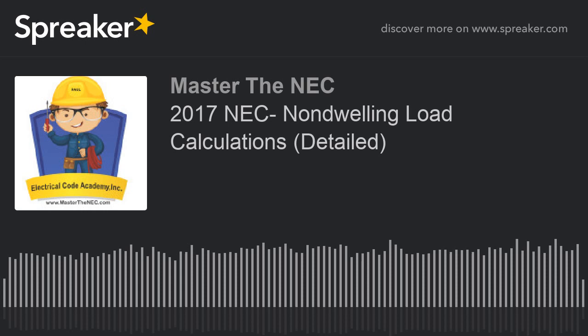Now, that's our calculated amps. We know it now. So now we have to size the service. Okay, now we know that we got to have a conductor that's going to at least handle this calculation for this load. We already calculated the load. We know that. We know that we need to do this. And we know that 230.42(A) tells us that, and then we know that 215.2 tells us that we have to handle that load. And we've done the calculation. We kind of know what the load is. But let's say, just for random numbers, let's say we did all this and we ended up with 216 amperes. That's what it was. Let's just throw a number out there.